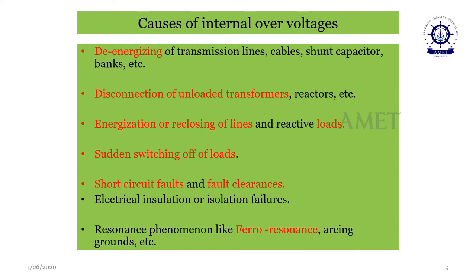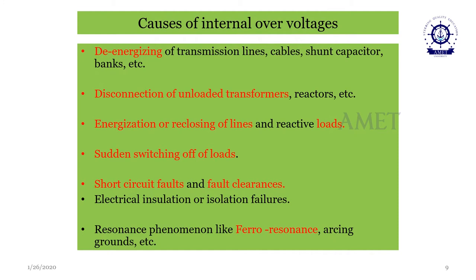So these are all the major causes. A very important phenomenon which often occurs in the power system is resonance, because our electrical network is non-linear in nature and almost 100% of our network consists of inductors and capacitors, energy storing elements, and that creates a lot of problems in the transmission system. We call that by the technical terms ferroresonance and arcing grounds. And then we have another cause too, called current chopping, which very often occurs due to the operation of circuit breakers. These are all the major causes of internal overvoltages. This has to be mitigated.